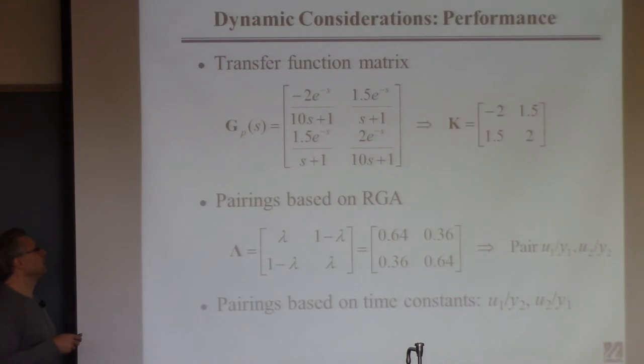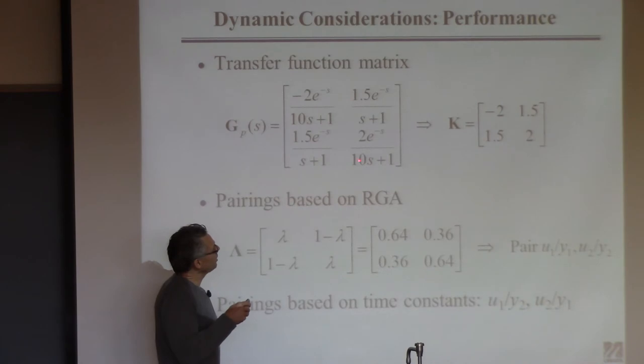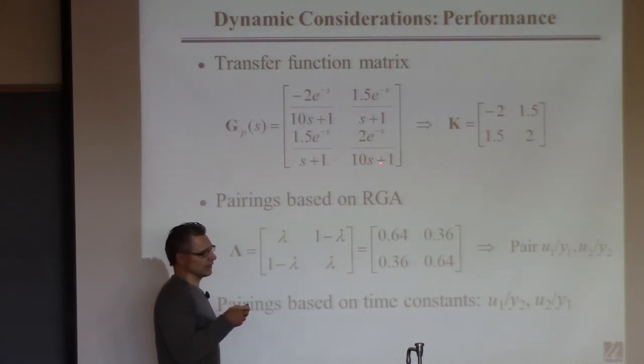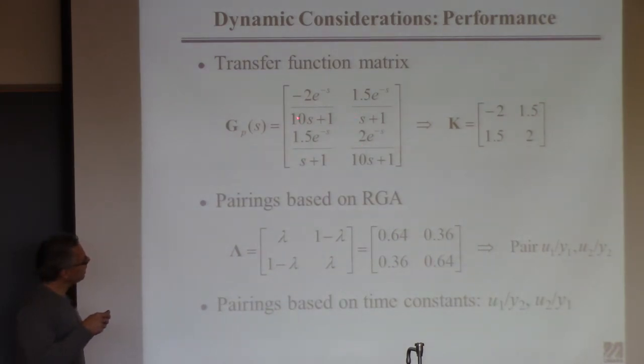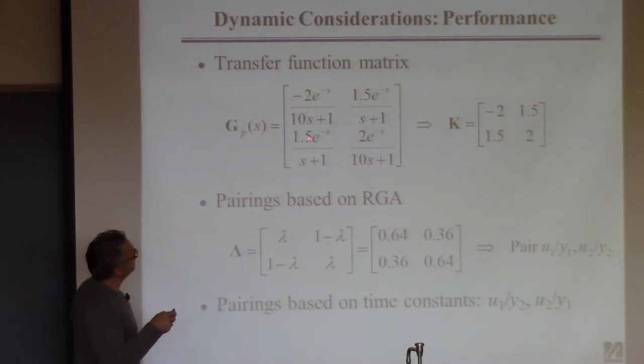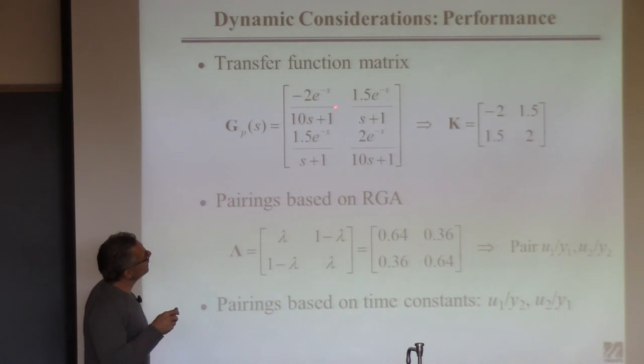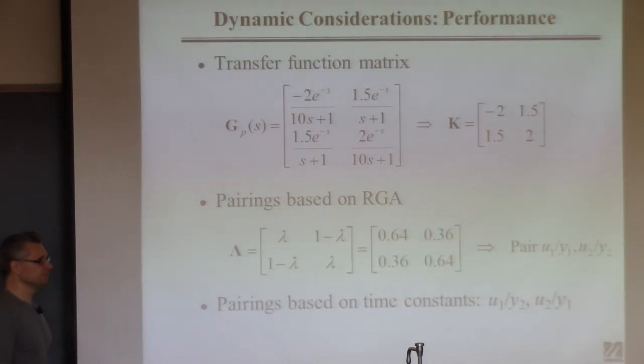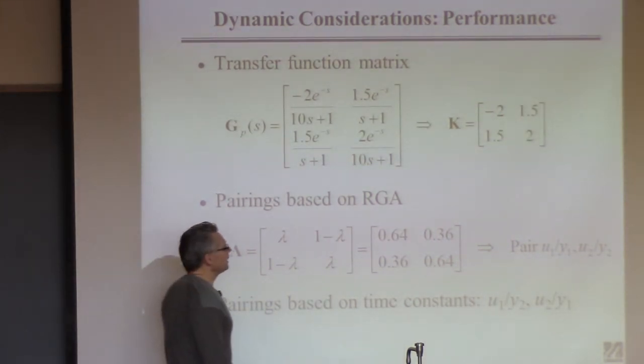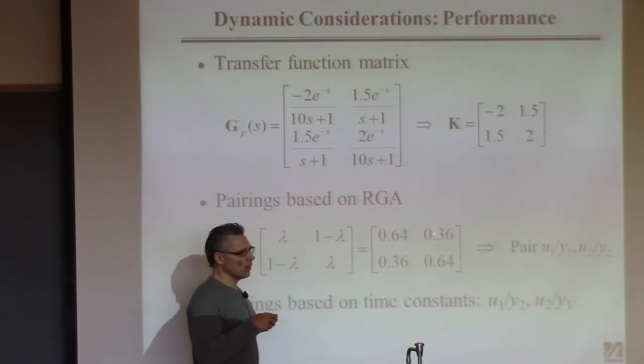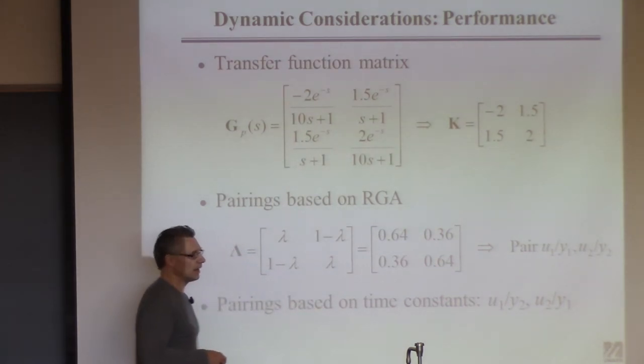Hopefully you've learned that the time constant of the process determines how quickly you can do control. If the process has a large time constant, you have to settle for slow control. The argument here is these time constants are actually a lot smaller than those, so you should probably do control based on those — small time constants are good. This is a case where you'd do your RGA, do your pairing, and then look and reconsider. Since these RGA numbers are relatively close and not negative, you might use the other pairing instead.